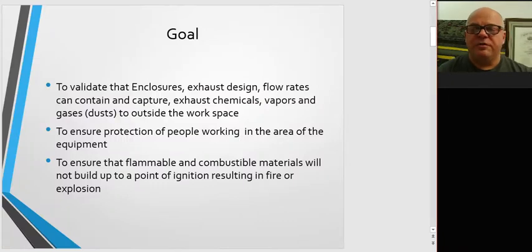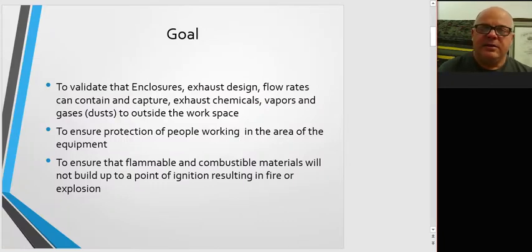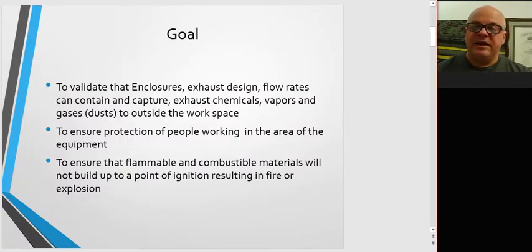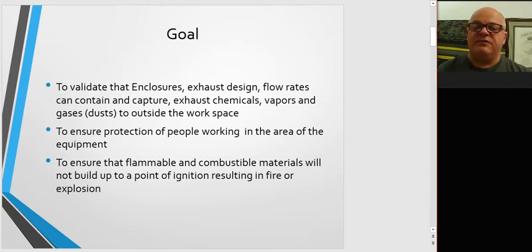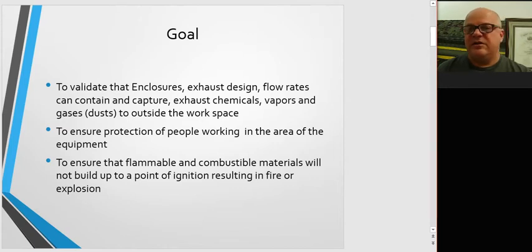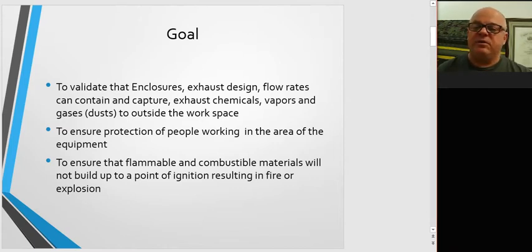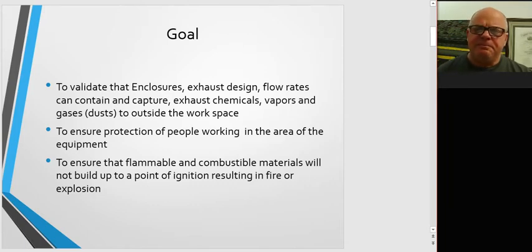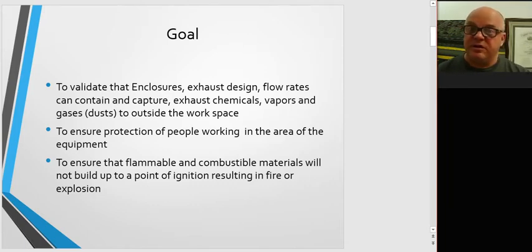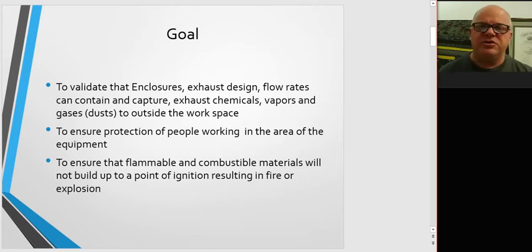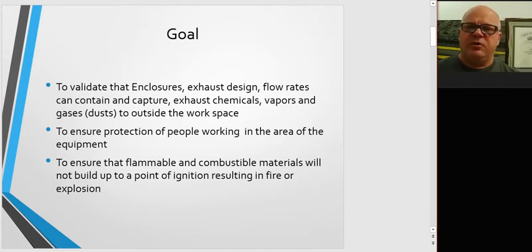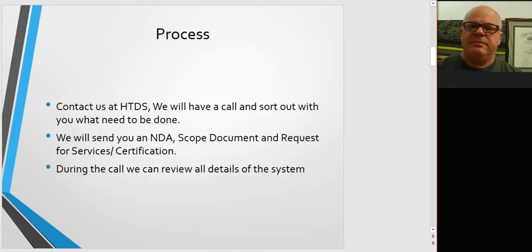First off, it's the goals for tracer gas testing. What we're validating here and testing to prove is that the enclosures, the exhaust design, the flow rates, and everything else can contain and capture exhaust chemicals and vapors and gas to outside the workspace, and do it in such a way that we prevent anyone from being exposed to toxic chemicals and prevent fire or explosion in the equipment or workspace.